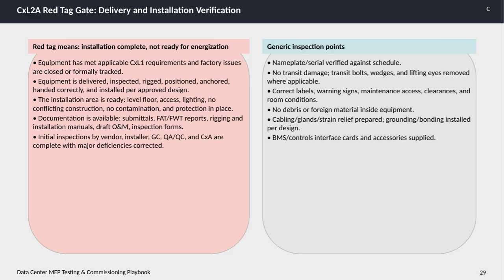Maintenance access is clear, sufficient clearance is provided, and room conditions meet requirements. Inside the equipment, there must be no debris or foreign materials. Additionally, cabling, glands, and strain relief should be properly prepared, with grounding and bonding installed exactly as designed. Finally, all building management system and control interface cards and accessories need to be supplied to complete the setup. This thorough verification process is critical to ensure a smooth transition into the next stages of commissioning and energization.